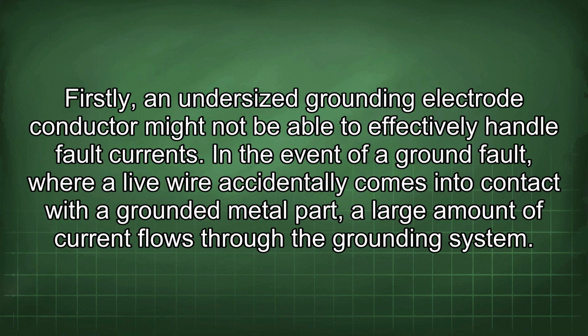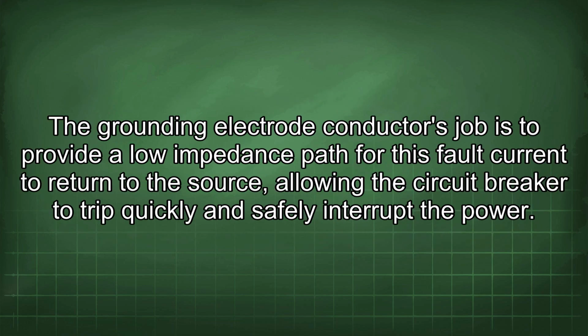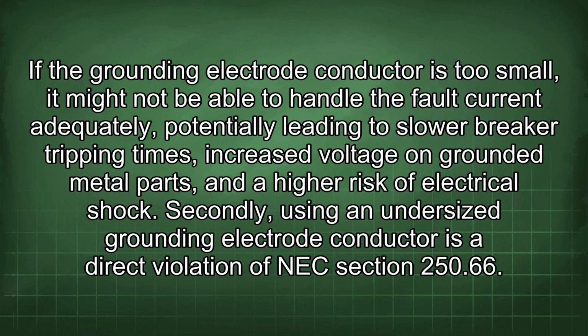In the event of a ground fault, where a live wire accidentally comes into contact with a grounded metal part, a large amount of current flows through the grounding system. The grounding electrode conductor's job is to provide a low impedance path for this fault current to return to the source, allowing the circuit breaker to trip quickly and safely interrupt the power. If the grounding electrode conductor is too small, it might not be able to handle the fault current adequately, potentially leading to slower breaker tripping times, increased voltage on grounded metal parts, and a higher risk of electrical shock.